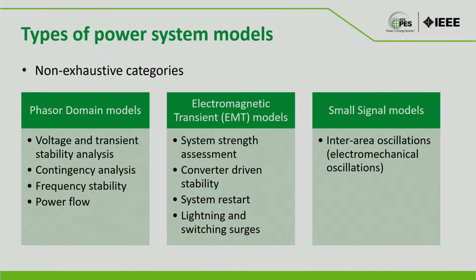These are some of the models which can be used for system restart. If the system goes black, you need to start it up. How do you do that? You first have a model, and you look at it: okay, I want to start this generator, pick up this generator transformer, pick up this line, then pick up this load, and go in this direction picking up the rest of the load. So you can use the electromagnetic transient model for system restart.